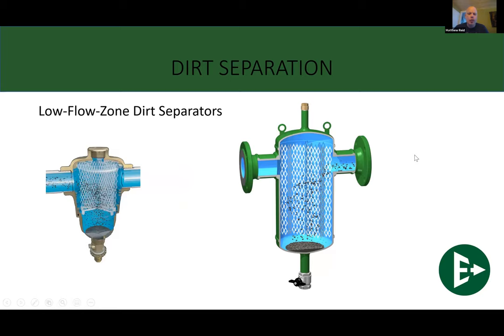Then we get into these guys. These are your low flow zone dirt separators. So these guys, imagine you took that air separator and you just flipped it on its head. Now, with regards to getting the air out, it was using gravity for the most part to have that air coalesce and climb that media out the top, where it blows. Now with the dirt separator, kind of the same thing happens. As the dirt particles are coming in through a system, they hit whatever media is on the inside of your dirt separator, and then gravity takes over. As you slow down the velocity of this dirt particle going through, then gravity takes over. Whatever dirt particle is in there, for the most part, and we'll get to this, it's going to be heavier than the water medium that it is flowing in. So as you slow its velocity, it is going to fall to the bottom.